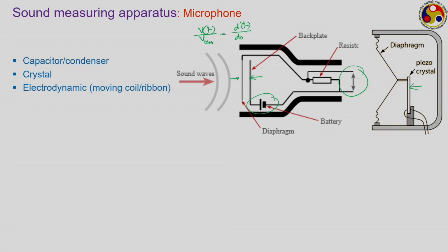So, a very simple working principle, and we can keep this one in direct contact with the diaphragm and the element, this crystal, and we can easily get a high quality measurement.